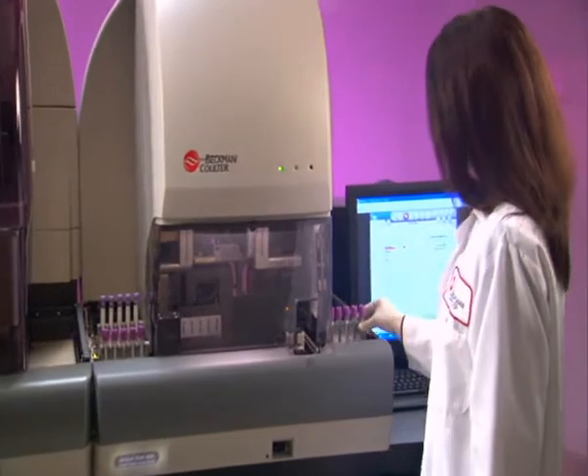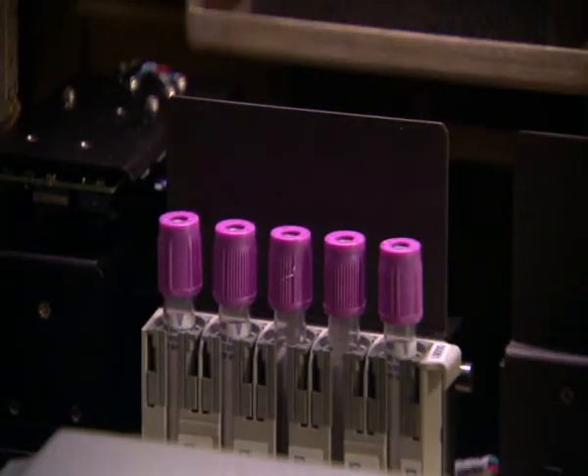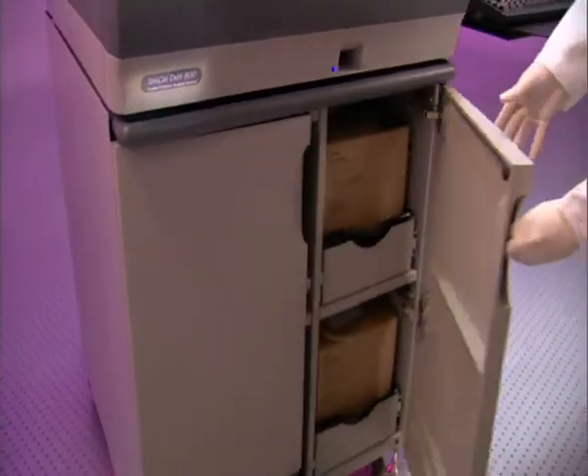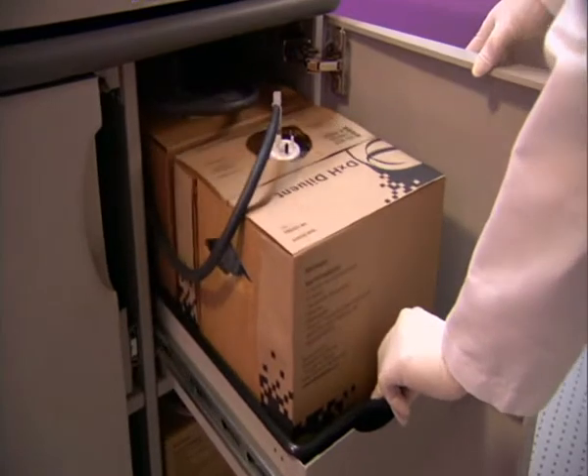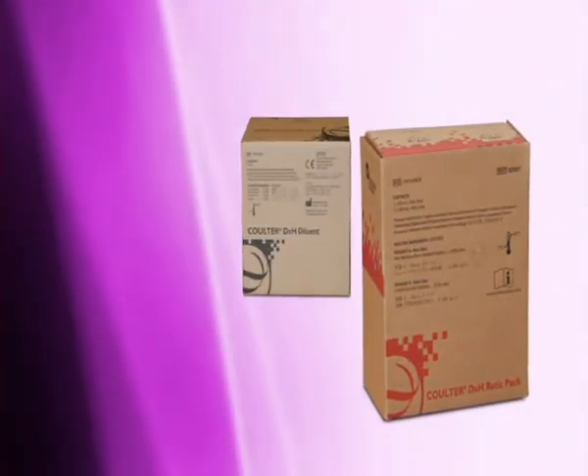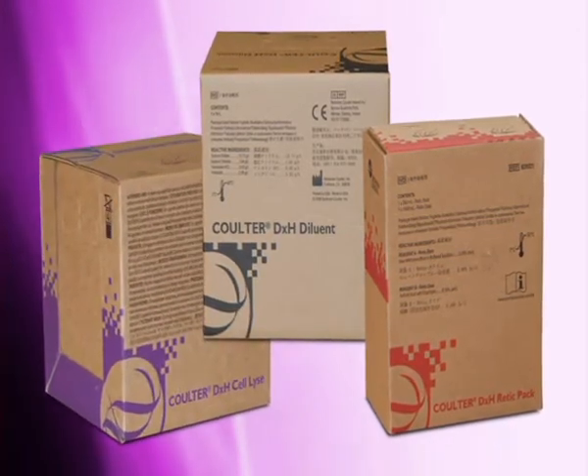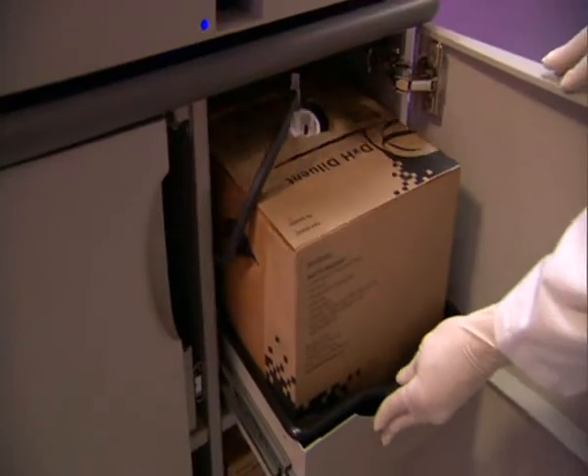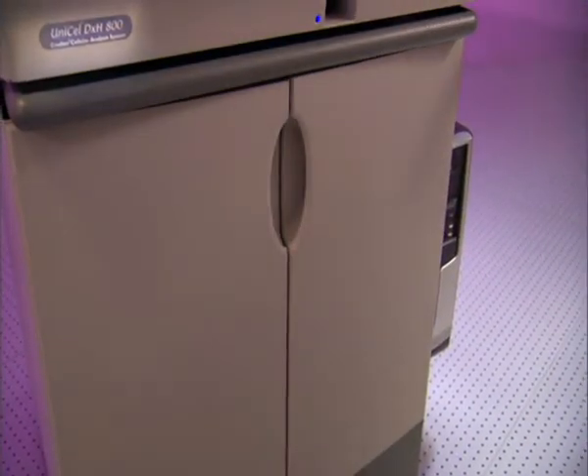Using a modular architecture approach, no pinch valves, and reduced reagent consumption, the analytical module of the UniCel DxH 800 was designed to be a highly reliable workhorse. Consumable packaging has been redesigned to take up less space and reduce storage costs. The new 10-liter containers reduce the potential for waste, and their light weight meets occupational requirements for lifting. The packaging itself is also recyclable to help protect the environment. The optional DXH floor stand helps organize consumables and makes changing reagents easy.